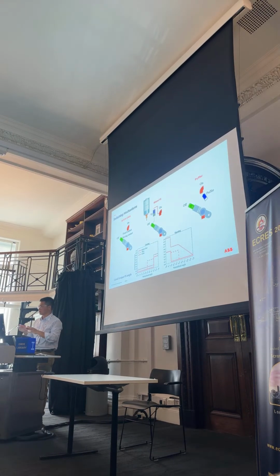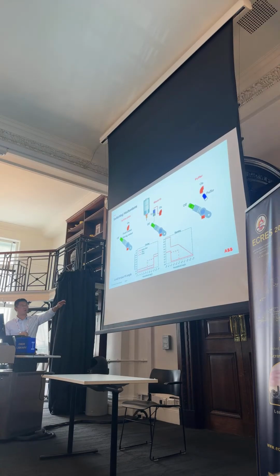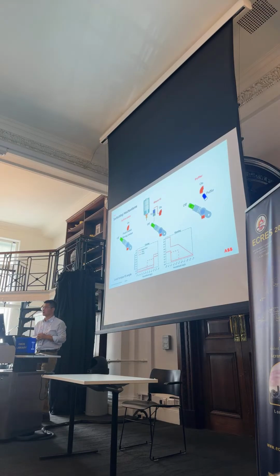From a mechanics simulation point of view, here is the loading profile of all these switching mechanisms. You can see the split plate has the lowest torque against angle, because it's only the weight and friction force inside. For the shunt VI version, we have all of the split plate effect, but also need this handover mechanism — that's the jump here, which is somehow the handover to the vacuum interrupter, giving a sudden jump of torque.